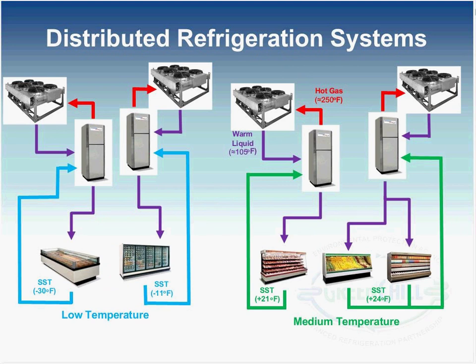Thank you. Just to kind of give a better idea of how these things would be laid out in terms of matching to the load and getting the energy benefit from using multiple units, this diagram kind of displays that. So if you look at the left-hand side, you have the low-temperature section, and typically we see wide island frozen cases and reach-in door cases. By matching the units and the compressors to the load that they're refrigerating, you can get energy benefit by having the compressors not work as hard on the loads that have lower compression ratio requirement than those that have a greater one. For instance, the door cases would run at a warmer temperature than the frozen food wide island case.